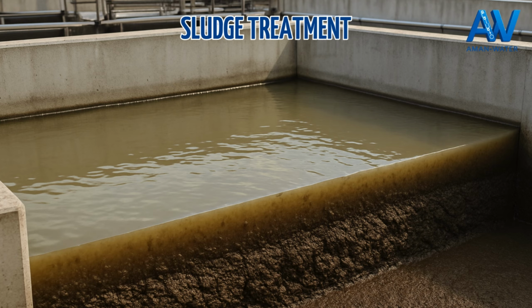The first step is thickening. This consists of increasing the concentration of dry matter by removing part of the free water contained in the sludge. This step can be carried out by simple sedimentation or using equipment such as gravity tables or flotation units. Thanks to thickening, the dry solids content often increases from 1% to around 6 or 8%. The less water there is, the more efficient the rest of the treatment becomes.